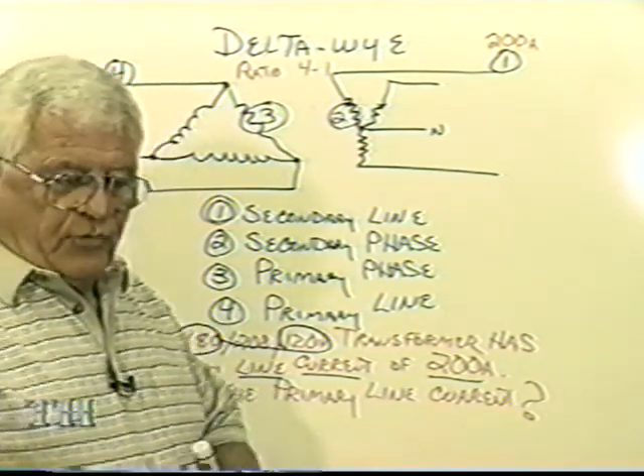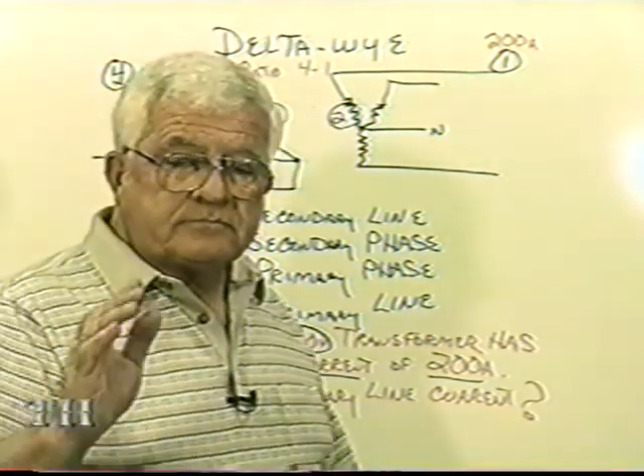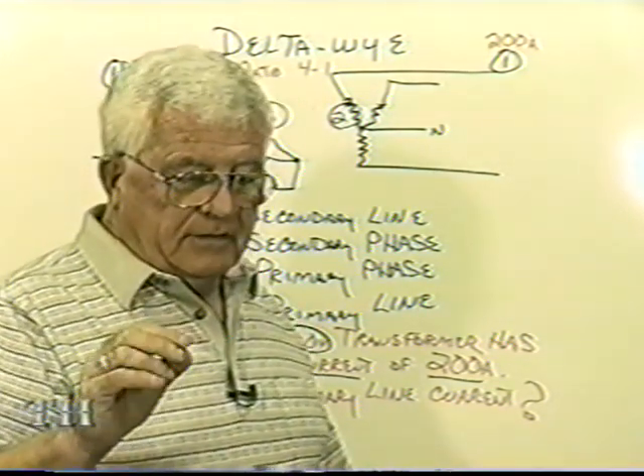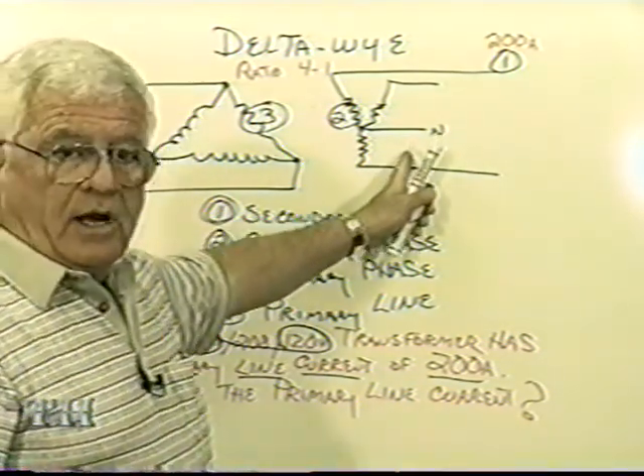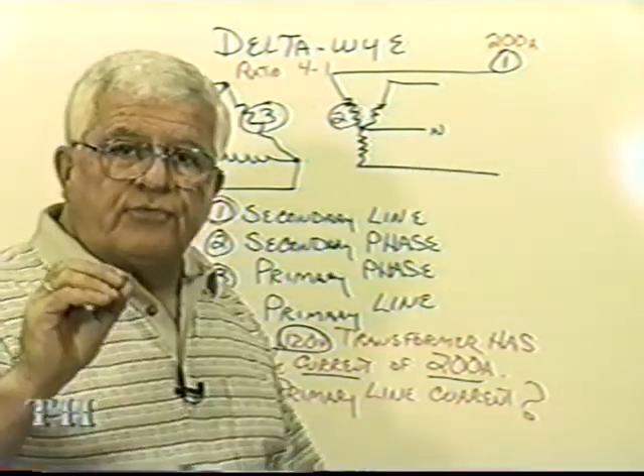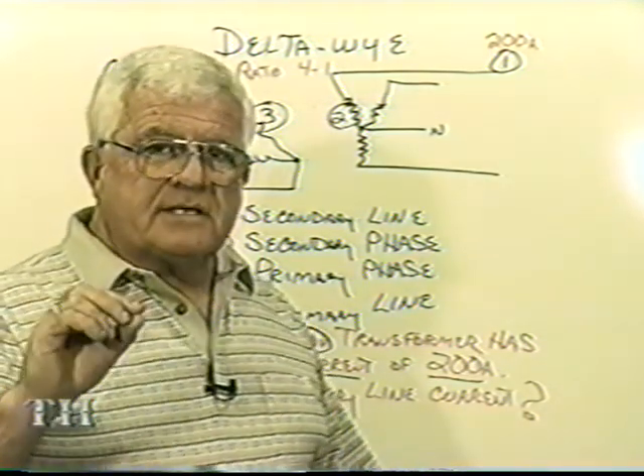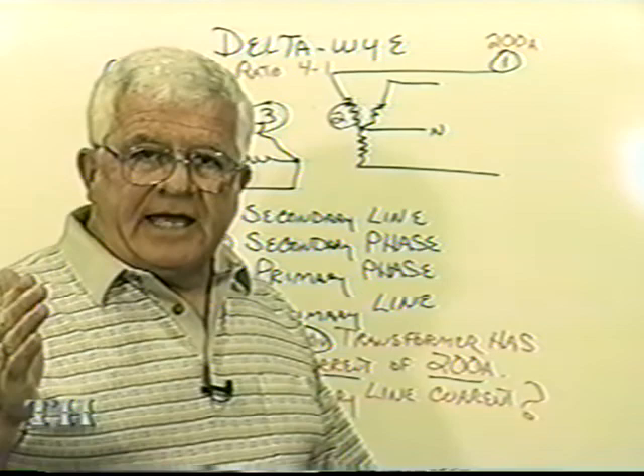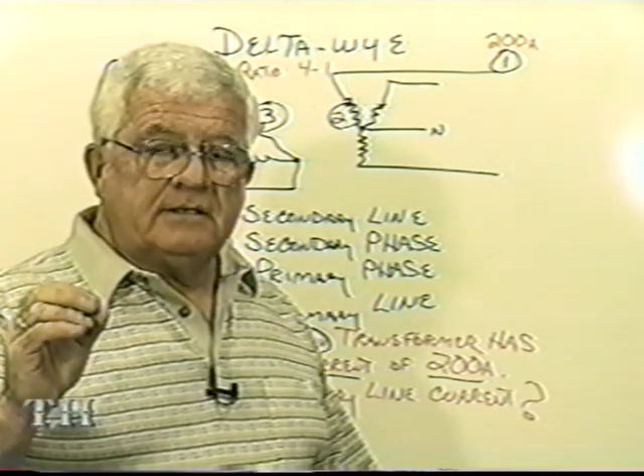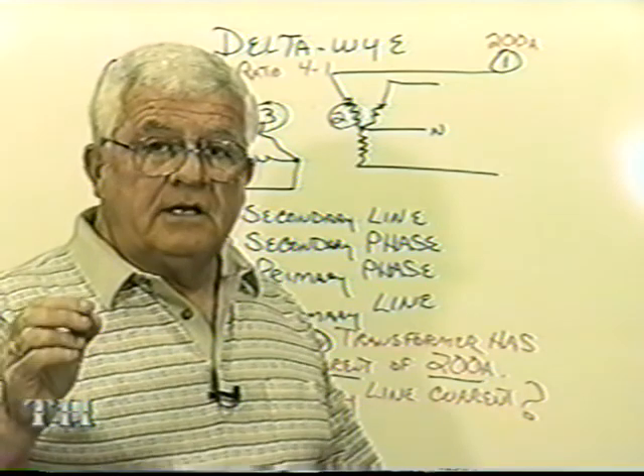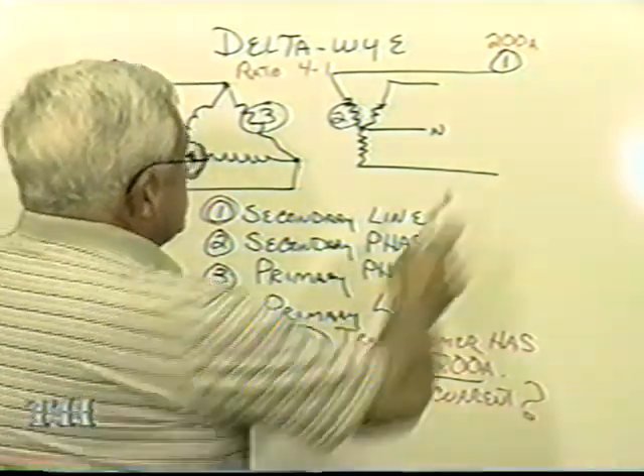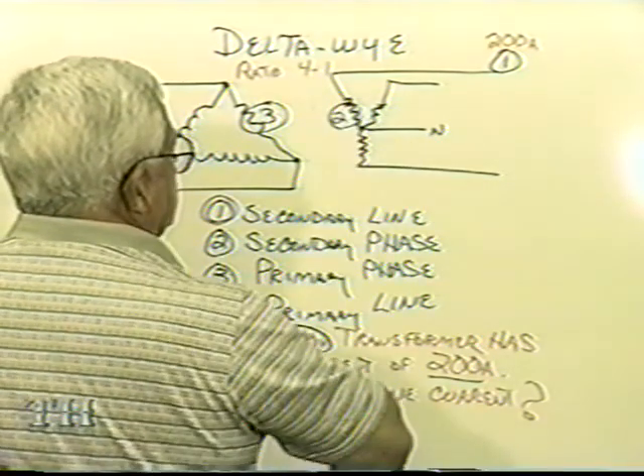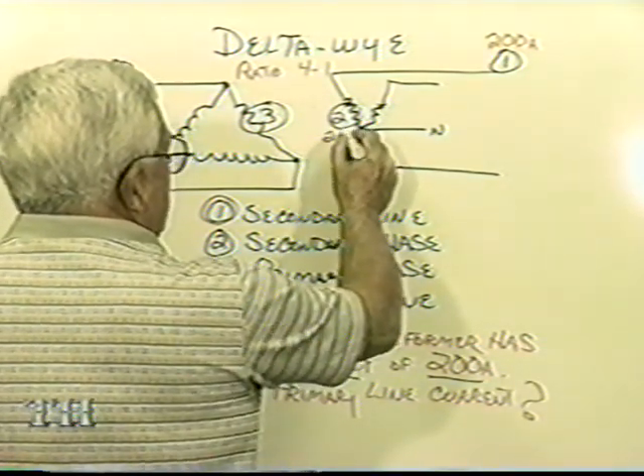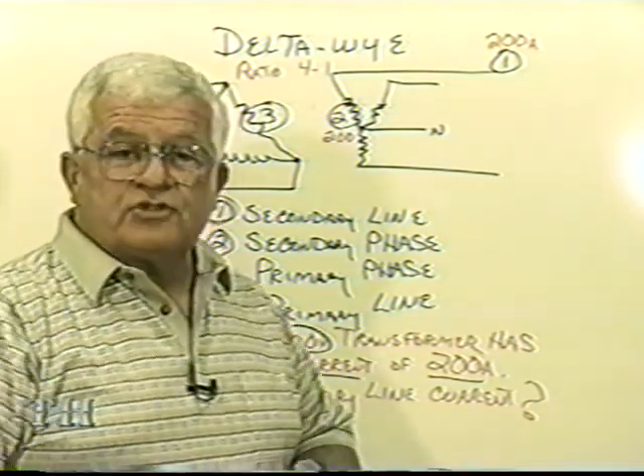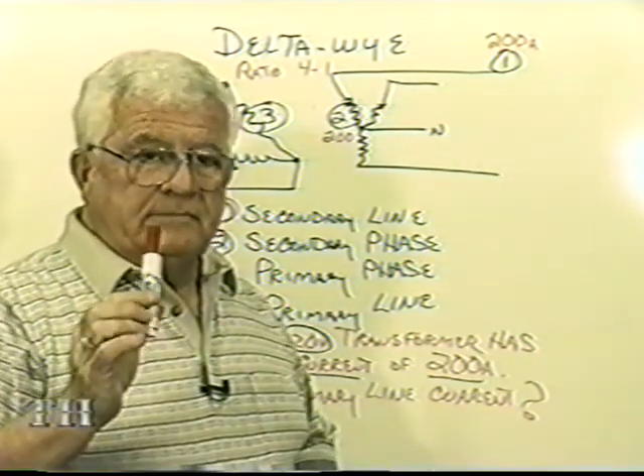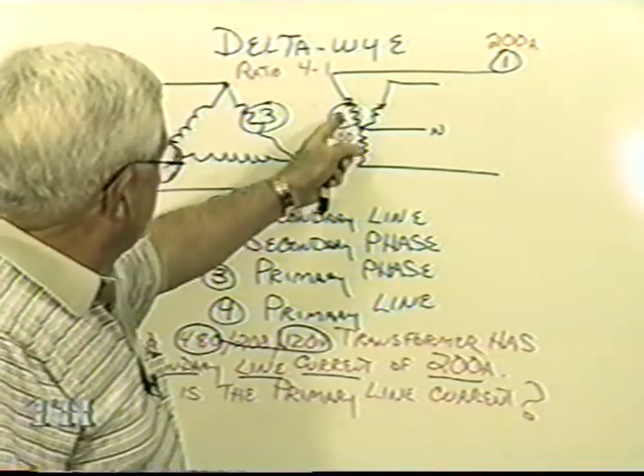Now, with your format that came with sheet 1, watch. Go to your format. Is this a delta or Y? It's a Y, so you go to your format for a Y. What does it say on a Y, that the line amps and the phase amps... does it say same? Yes. So what you would do is just pencil in: this 200 amps is going to come right down here and wind up at position 2. You have the same 200 amps at position 2. Now here's where it's important when we go from 2 to 3.